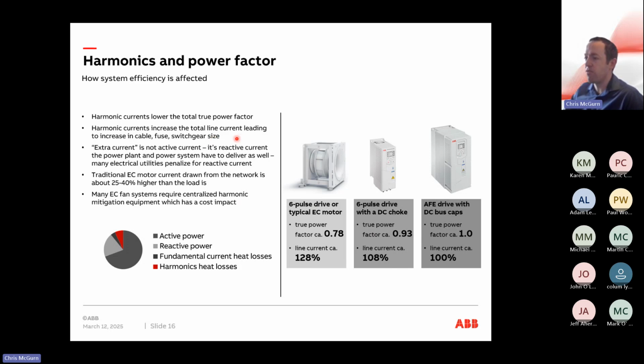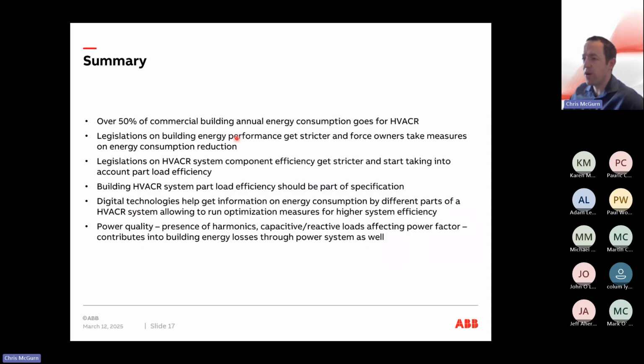So it's something to watch out for, especially if you're dealing with large kilowatt motors and maybe you're having brownouts and the like on sites that have large kilowatt pumps and fans. So in summary, over 50% of commercial buildings' energy consumption goes towards HVAC-R. There's legislation in place that is getting stricter, forcing people to keep an eye on their energy consumption. Building HVAC-R systems' part load efficiency should be a part of the specification. So your design should include an understanding of how your actual system works.